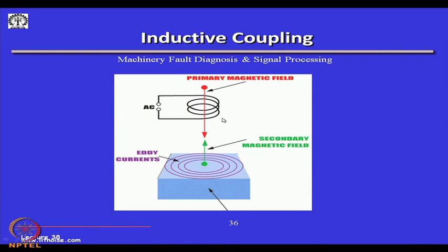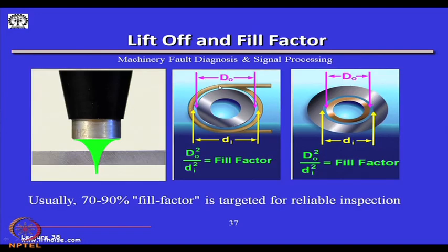There is inductive coupling between the primary coil and the secondary magnetic field because of the eddy current — this coupling is what we sense and use. There is another parameter to be careful about: how close should the probe be brought to the surface — defined as the lift-off and fill factor. The fill factor is D_outer squared divided by D_inner squared, and usually 70 to 90 percent fill factor is required for reliable inspection.